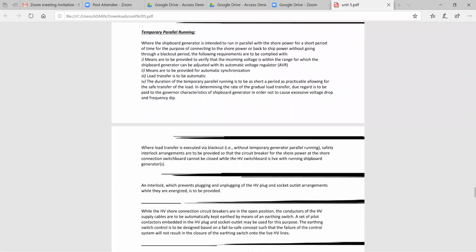Temporary parallel running is one of the important ones, where the shipboard generator is intended to run in parallel with the shore power for a short period. So temporary parallel running operations are performed. That means we have to verify that the incoming voltage of a generator is equivalent to the outgoing buses of the generator. The shipboard generator can be adjusted with the automatic voltage regulator. The shipboard generator operates at a certain voltage level, and the automatic voltage regulator also operates at a certain voltage level.